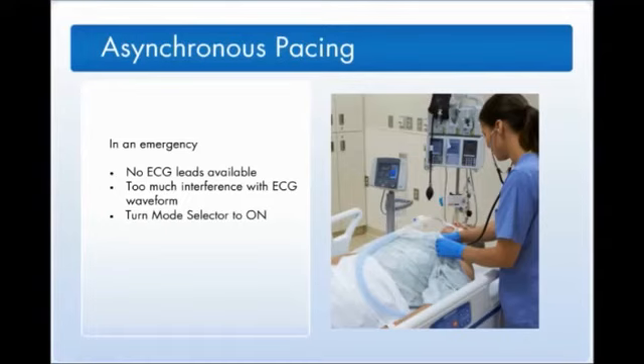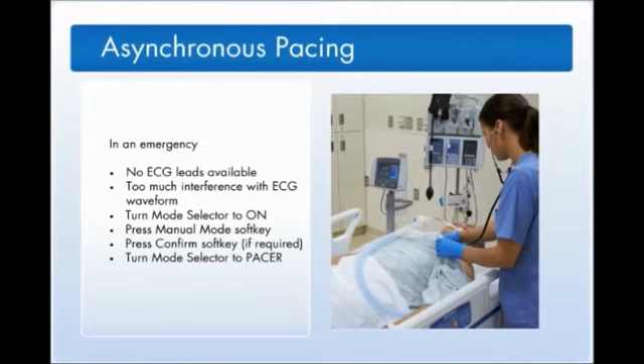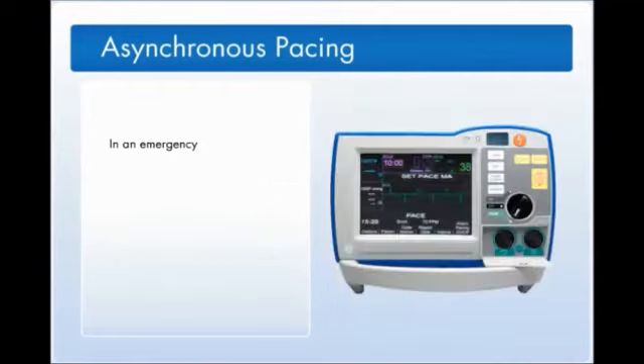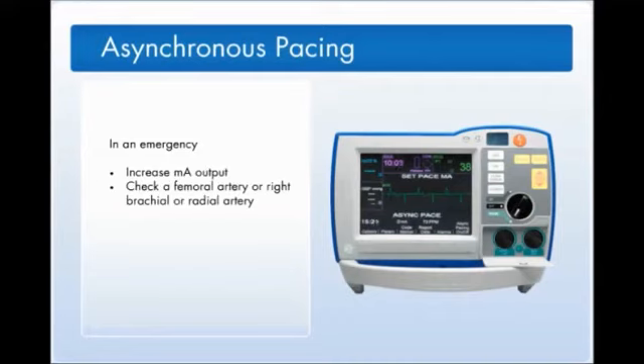Turn the unit on. Press the manual soft key. Press the confirm soft key. Then turn the mode selector to pacer. Press the async pacer on-off soft key. Increase the output until you are able to feel a pulsation at a femoral artery, a right brachial artery, or a right radial artery. The pacer will pace at the set rate independent of the patient's underlying rate. Attach ECG leads as soon as possible and turn off async pacer.